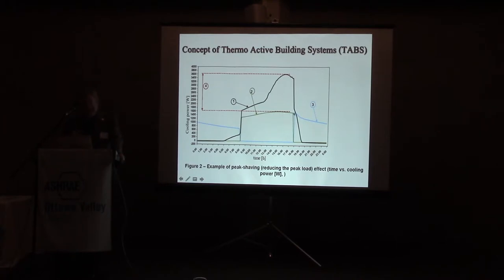That also means we are not controlling the temperature at a fixed level. We will have the temperature floating in this space, it will drift. Then, during that time, heat will be absorbed in the concrete slab. And then when people are gone during night time, we can cut down on the ventilation. And now we make the cooling on the water side. So we are removing now this heat that has been absorbed. So in the morning, the area under this curve here should be higher than what was generated.